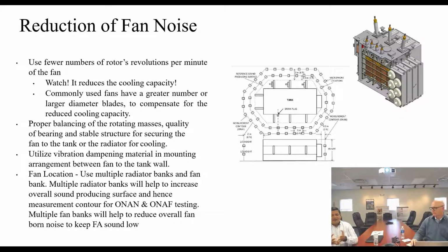The reduction of fan noise can also be achieved through the balancing of the rotating mass. As we know, there is a motor inside which is rotating the fan. So if we balance the motor, that means we have a good bearing and a stable structure for securing the fan, so the structure-borne noise from the fan itself can be reduced. Also, we can reduce the fan's noise or fan chattering by providing a proper sturdy mounting arrangement for the fans. And on the mounting arrangement we can also use vibration dampers, so that if there is any extra vibration coming from the fan, it can be damped through those dampers, and that's how we can reduce the sound effect of the fans on the overall transformer.